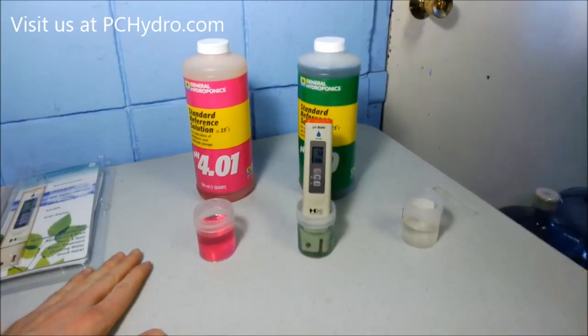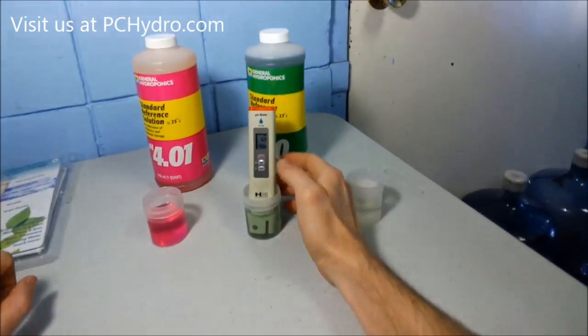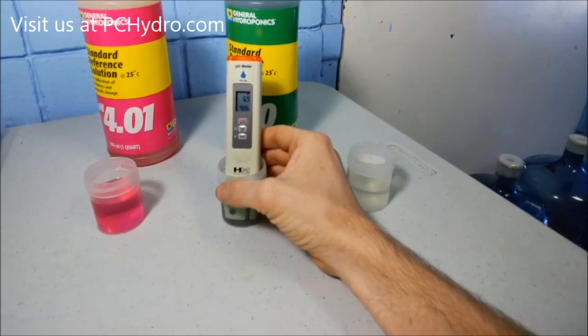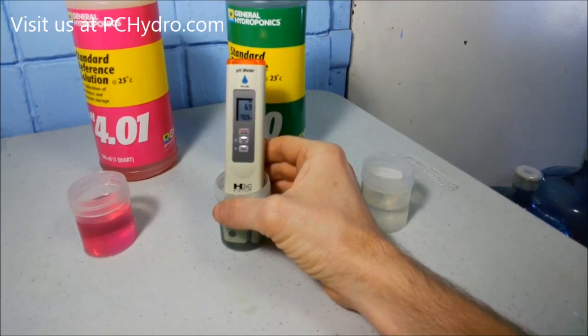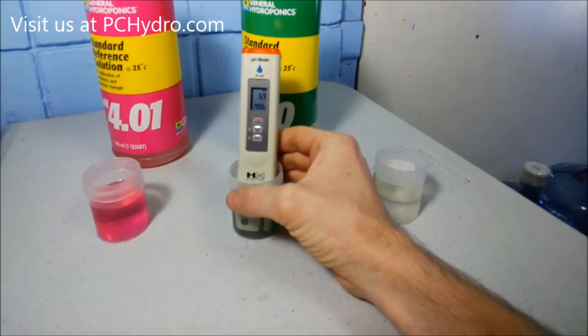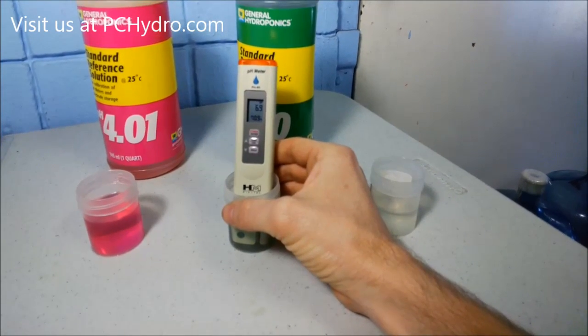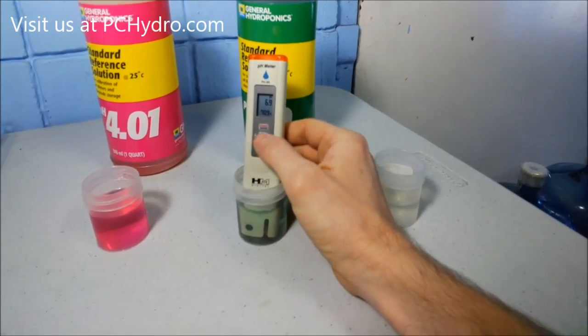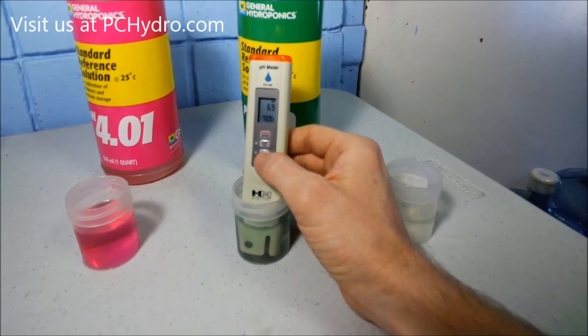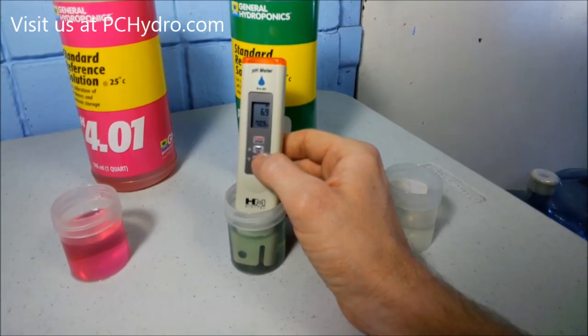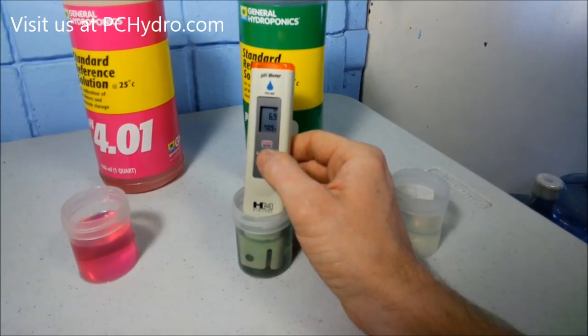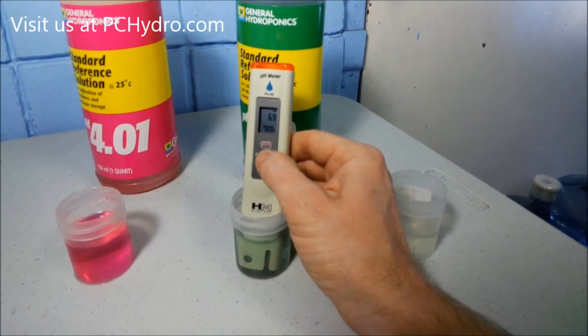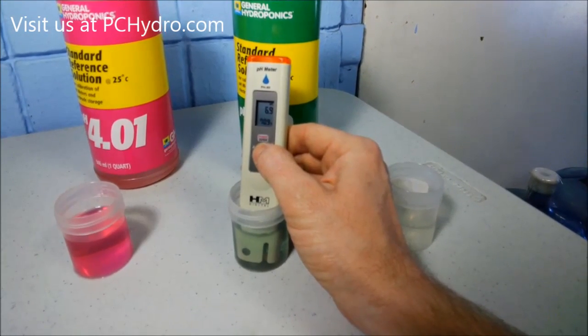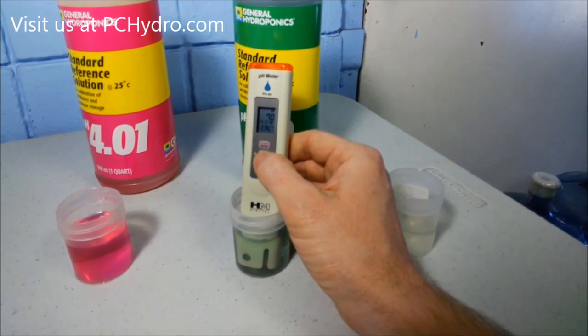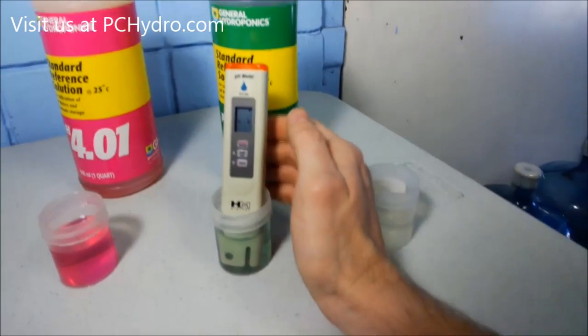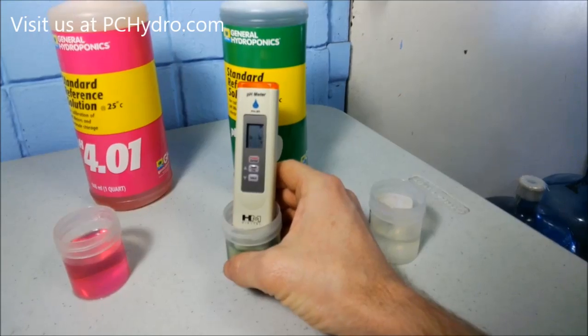We'll be right back. So we're back, and we're going to go ahead and calibrate the pen. The pen's reading 6.9, which is actually pretty good for the pen to be reading right out of the box. But we'll go ahead and calibrate it to 7, and all you've got to do is hold the temp cal button, which will start the calibration process. You just hold that button down, I think it's about 5 seconds, and the calibration starts, and it automatically will select 7.0 because it's pretty close to that number as it is.